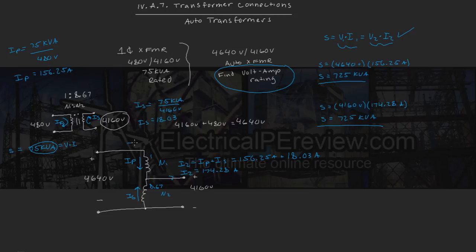Now to find our new autotransformer ratio, our N1 is going to be these two winding counts together. So we're going to have 1 plus 8.67, which gives us 9.67 to our output winding count of 8.67. We can clean this up a bit by dividing 9.67 by 8.67, and we get 1.12 to 1.